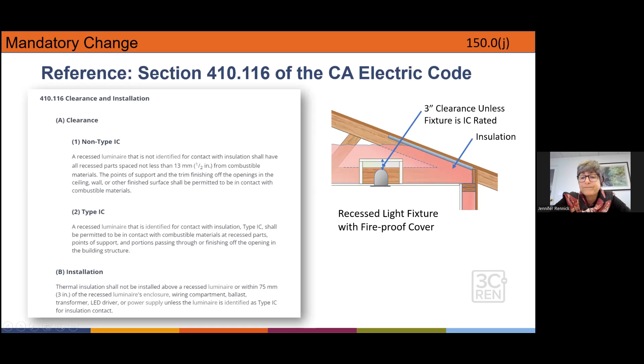So when the California Energy Code references the California Electric Code, basically, for us as architects or lighting engineers and designers, most of the time you're going to want to spec a lighting fixture that is IC rated, or insulation cover rated, called type IC. But if you don't, that fixture needs some way to be fireproofed with a cover, and there has to be 3-inch clearances around the housing, the wiring, and anything on the fixture that can get warm.